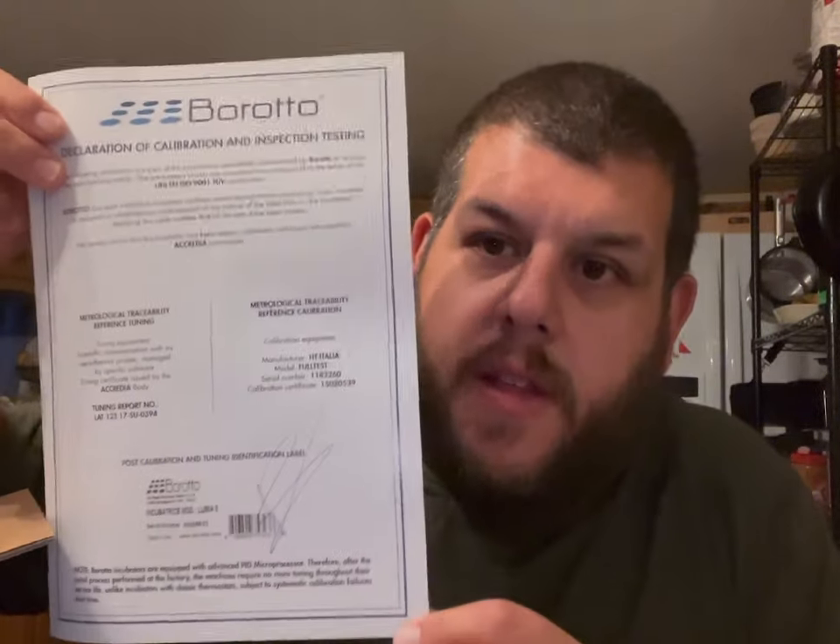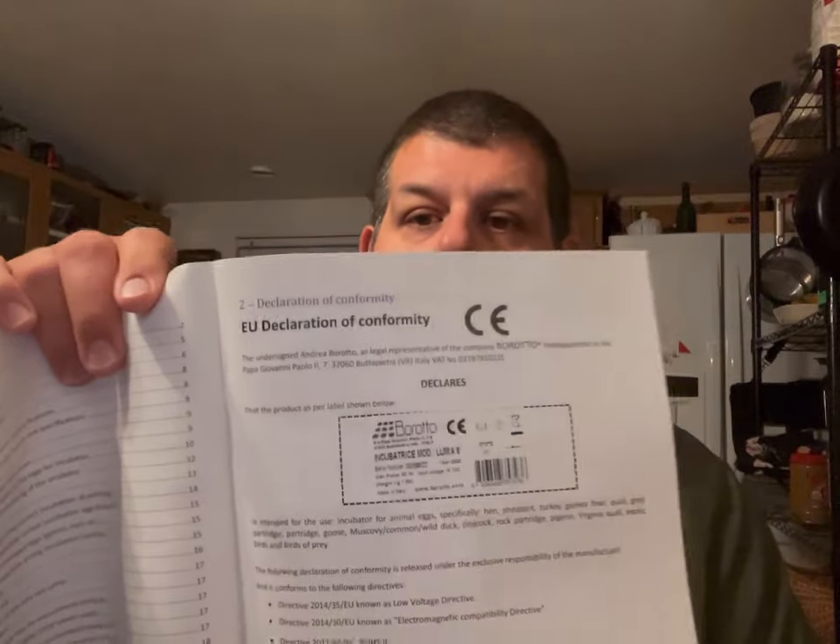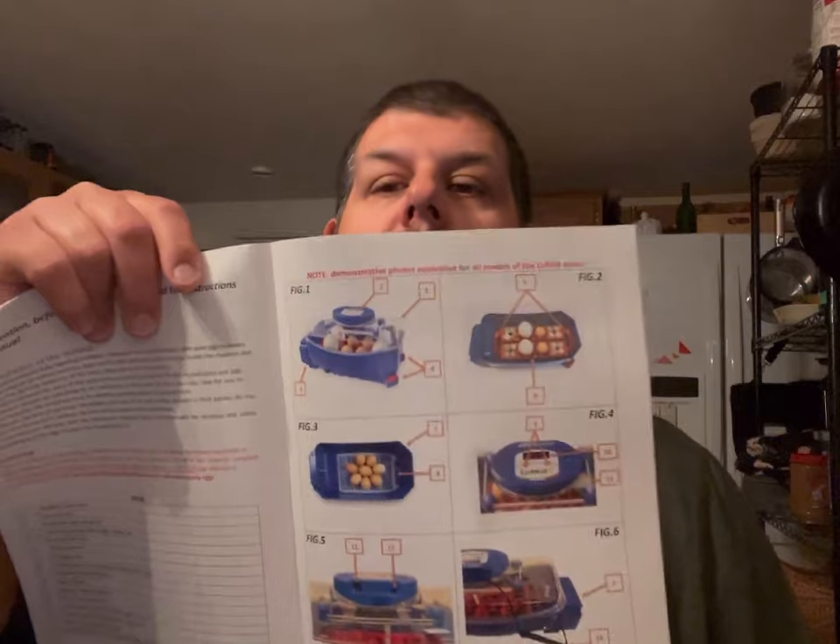I'm really excited about these because their reviews are just outstanding. Right off the bat you can tell you're in another league with these, because Borotto does this calibration sheet that they give you with the incubator. It has all the information: the tuning report number, the manufacturer who calibrated it, the model, the serial number, the calibration certificate, and the signature of the person who actually did the tuning and calibration. You're also getting a very well put-together manual with all the information you'd ever need, plus a declaration of conformity showing it's been tested through a pretty rigorous process.